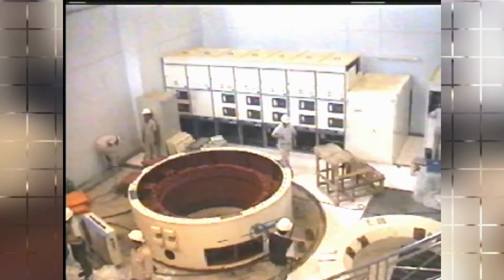The core of the generator is built up with high-grade, non-aging, thin, laminated silicon steel, each lamination coated on both sides after punching with an insulating varnish or other material to minimize eddy current losses. The laminations are adequately keyed or dovetailed to the stator frame and securely held in place by clamping flanges at each end to prevent looseness of laminations on the outer ends of the slots and the top and bottom of the stator.